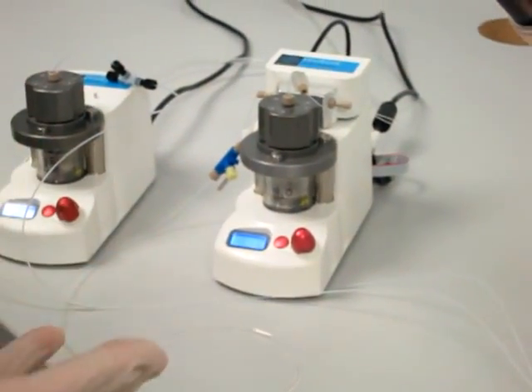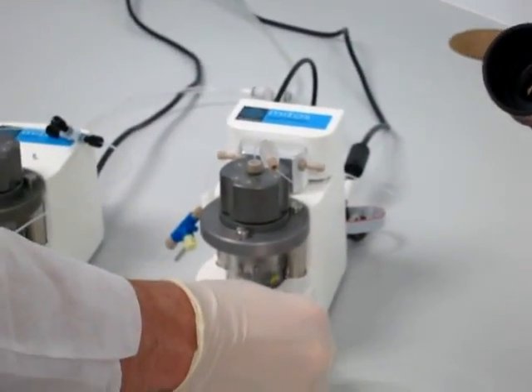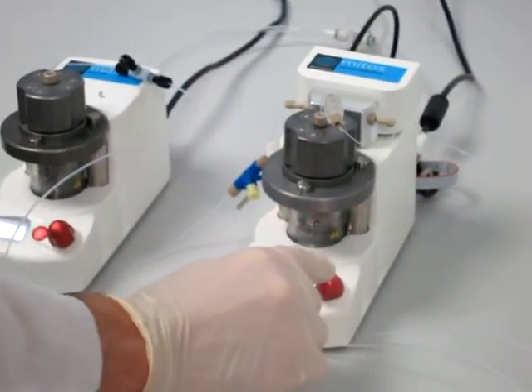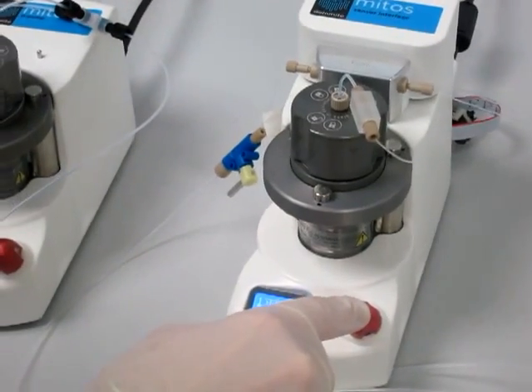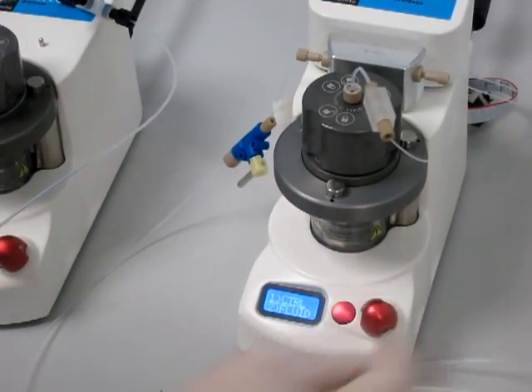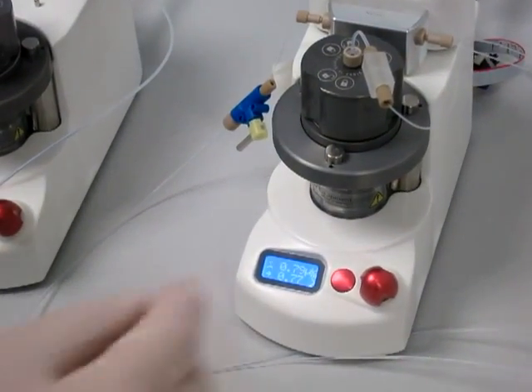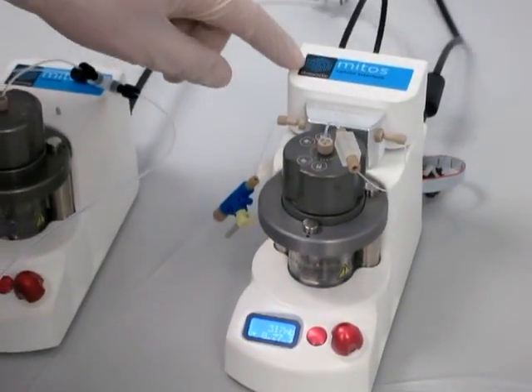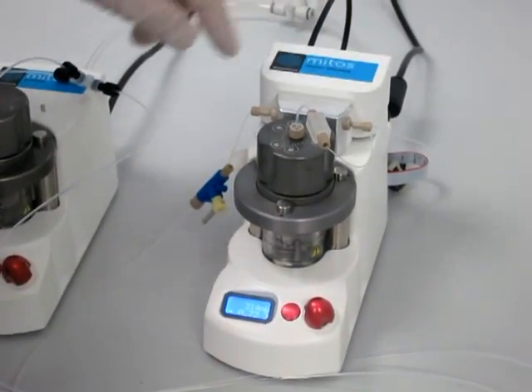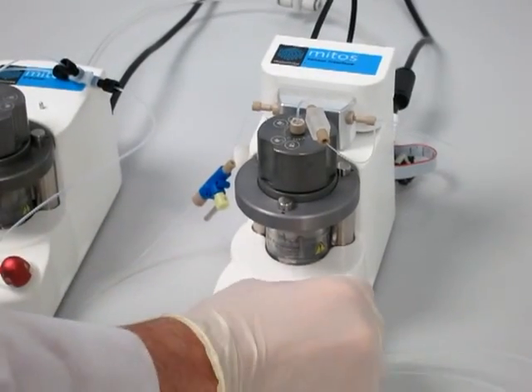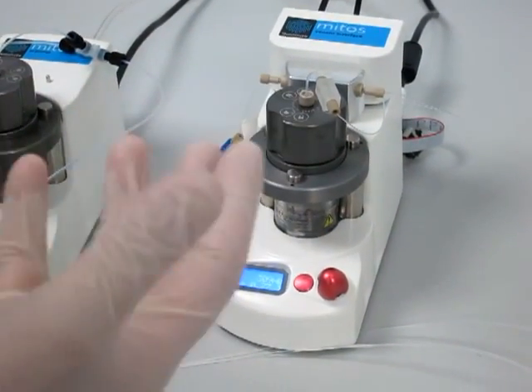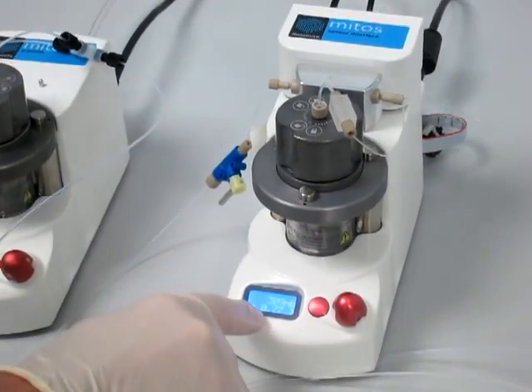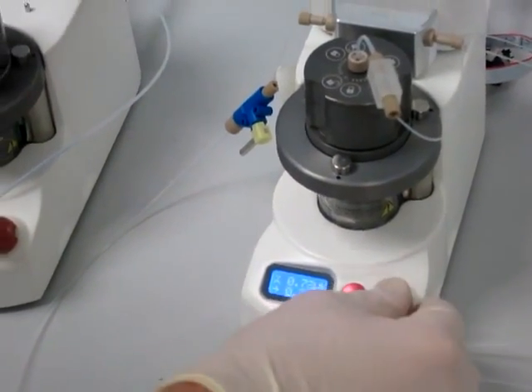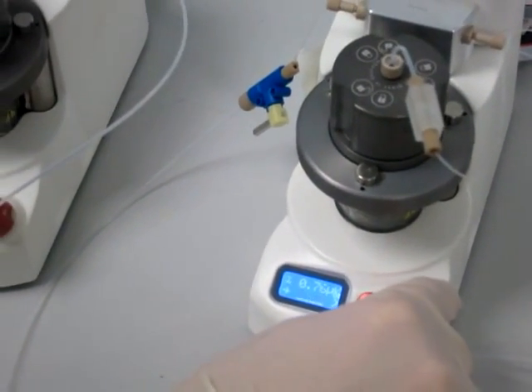So what I can do, if I come and have a look at the P pump, is switch from pressure control to flow control. Essentially I go to control, and I select flow control. What we've got on this P pump is a flow rate sensor. The flow rate sensor measures the flow rate, and we can change the pressure to achieve a particular flow rate. It's set at a flow rate of 0.77 microliters per minute. Unfortunately this is at the limit of the sensor.